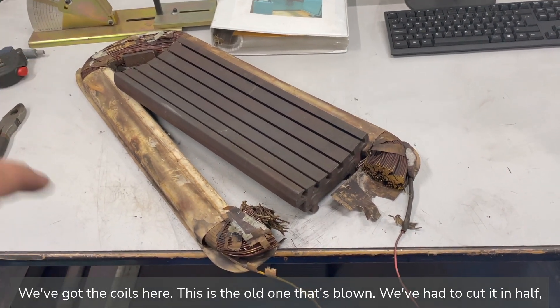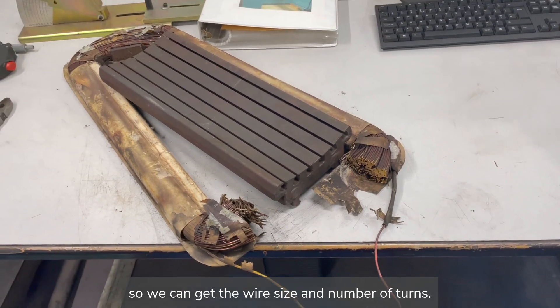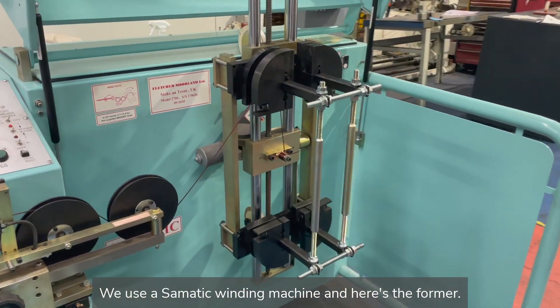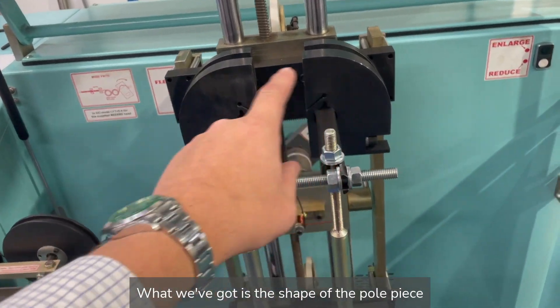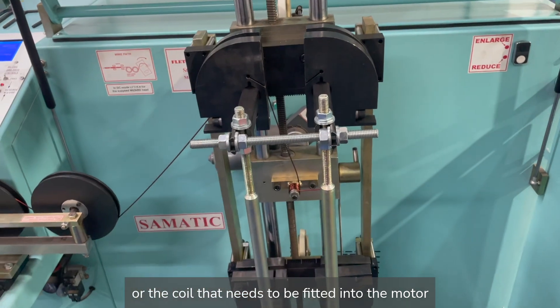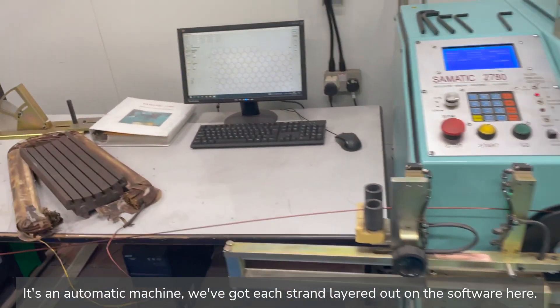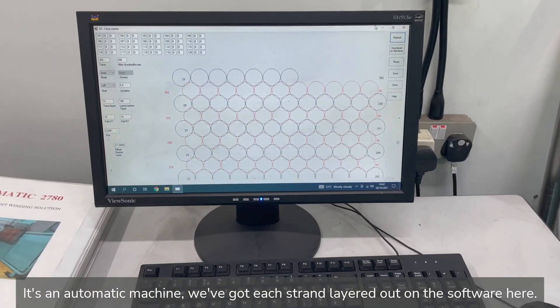We've got the coils here — this is the old one that's blown. We've had to cut it in half so we can get the wire size and number of turns. So the winding machine itself is this machine here; we use a Samatic winding machine and here's the former. What we've got is the shape of the pole piece or the coil that needs to be fitted into the motor, and as it's an automatic machine we've got each strand layered out on the software.